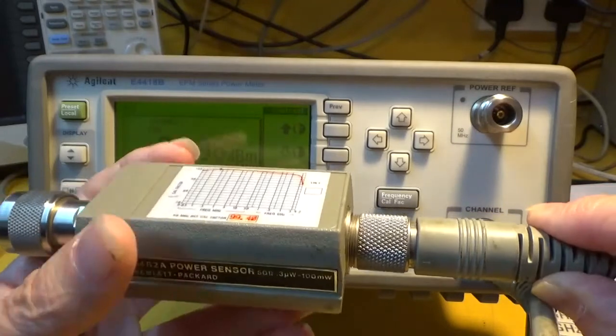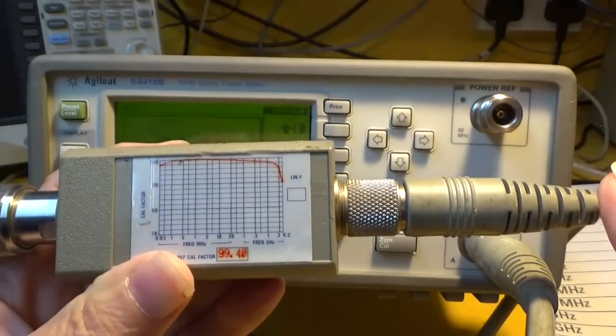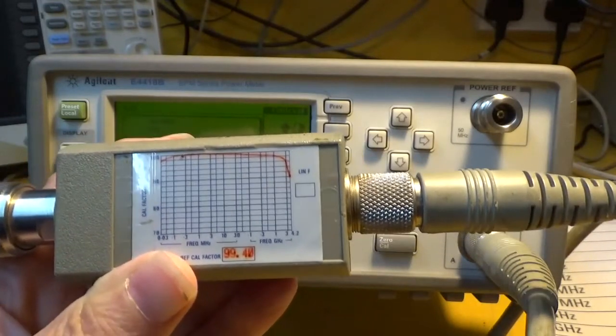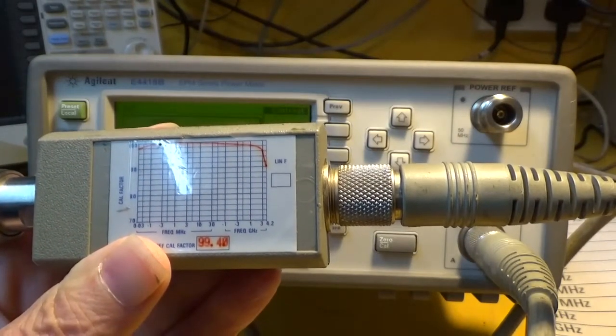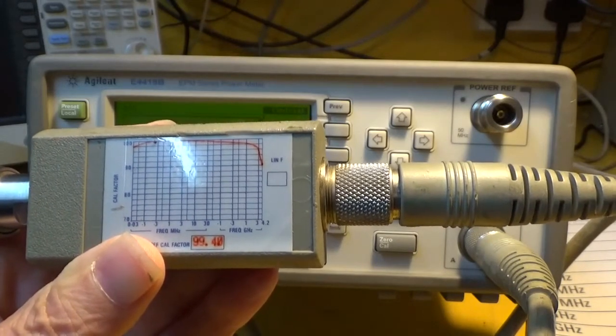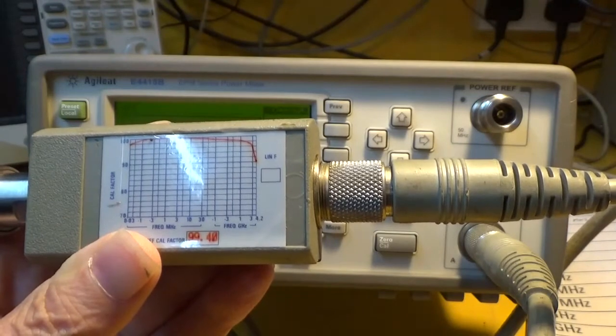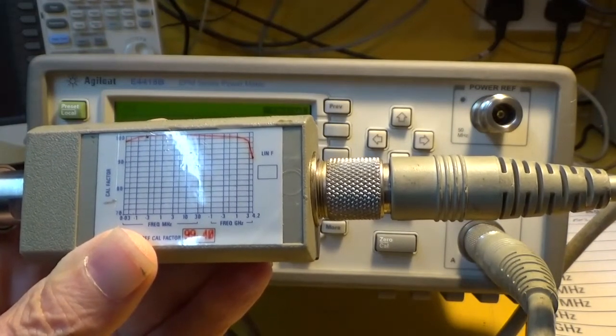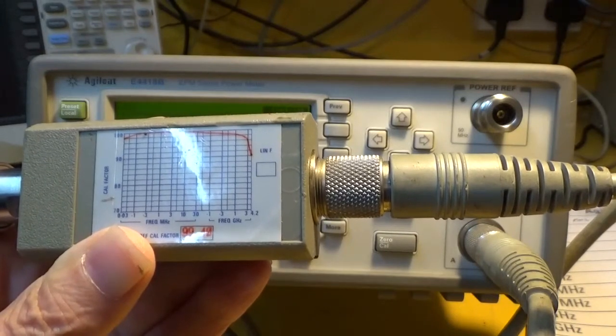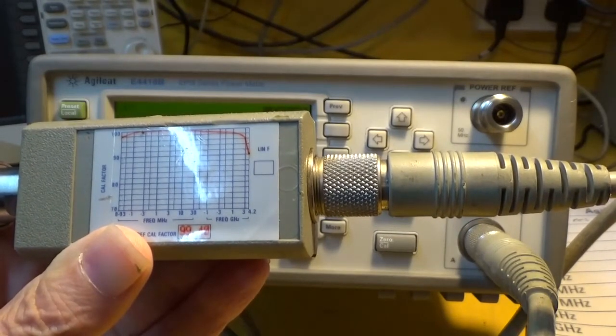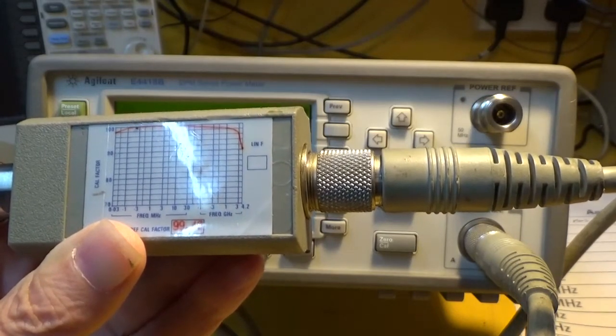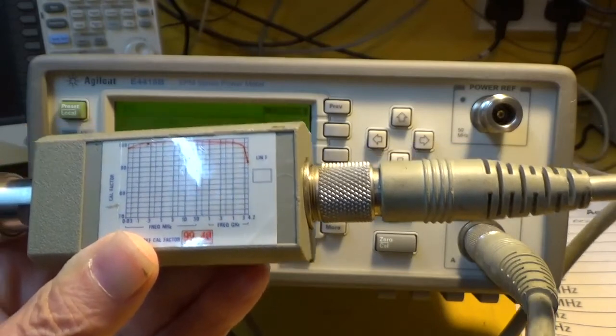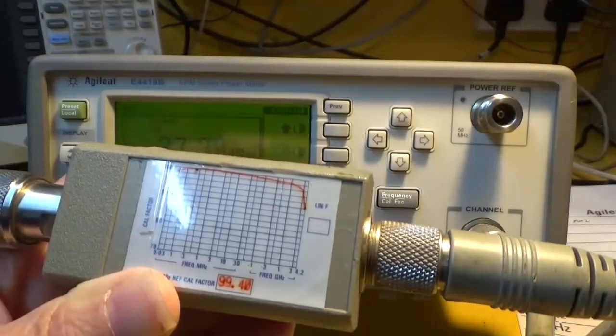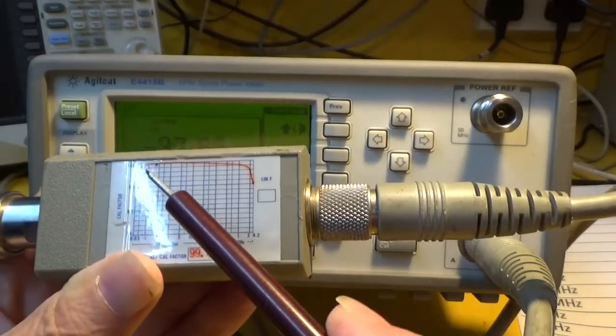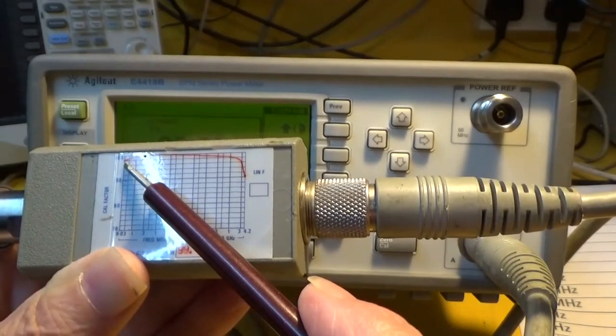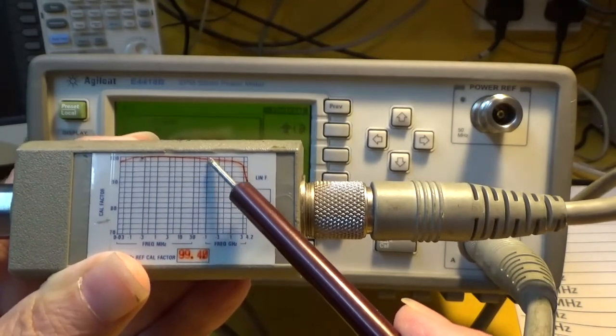And normally when you get these power sensors, they have a list of calibration tables on the back of the sensor. But this one's got a hideous little graph, because the response of the sensor will vary across its frequency range, and the frequency range on this one is 30 kilohertz. No, is it 30 kilohertz? Yeah. No, it's not. It's 100 kilohertz up to 4.2 gigahertz. And if I get something to point with, as you can see, it varies considerably over the range.